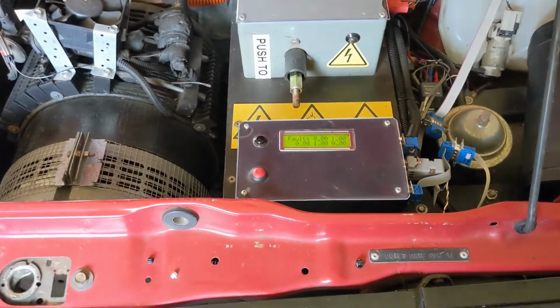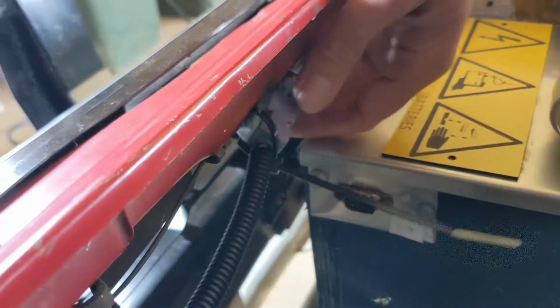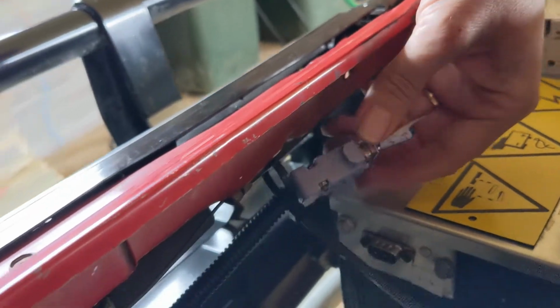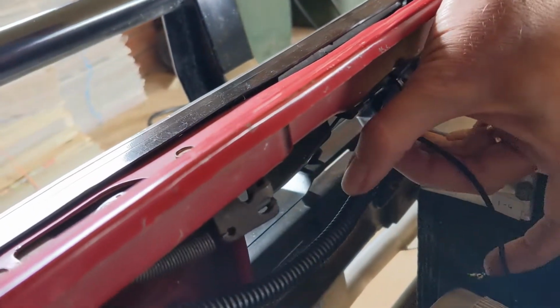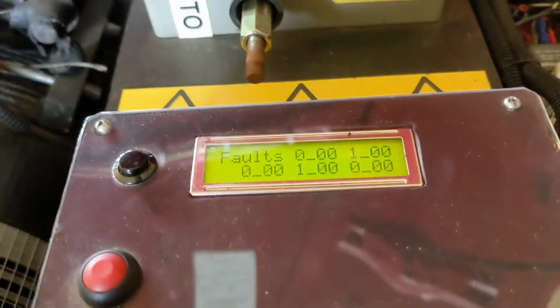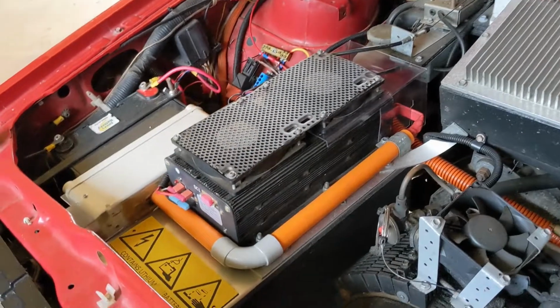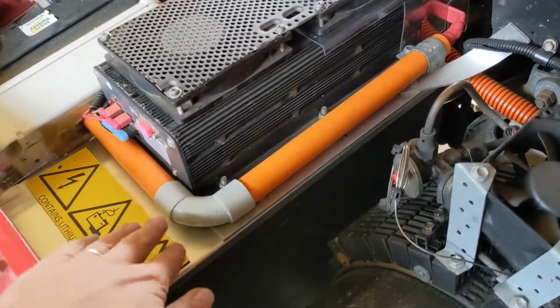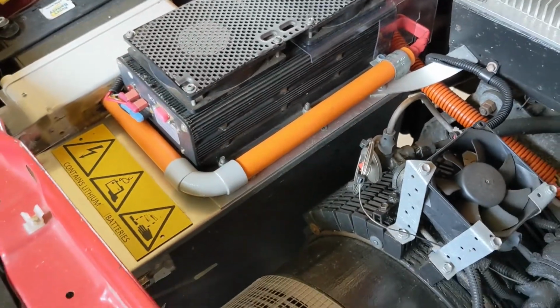So I've just been for a run with that bypass and the connector strung up here next to the motor. It was exactly the same as last time. No errors, no gaps in the data. This means that the problem is coming from inside that ridiculously hard to get into box.